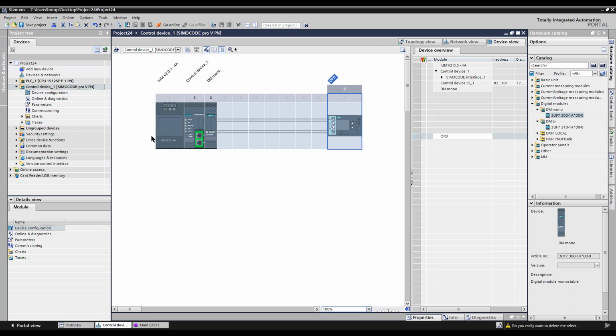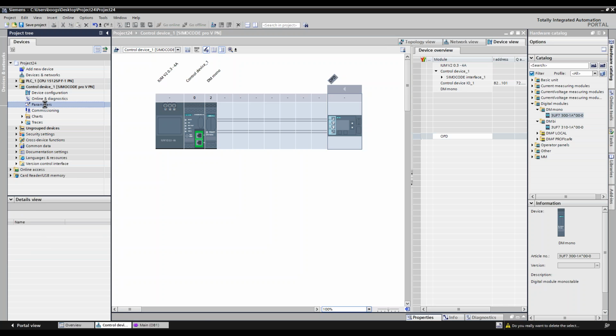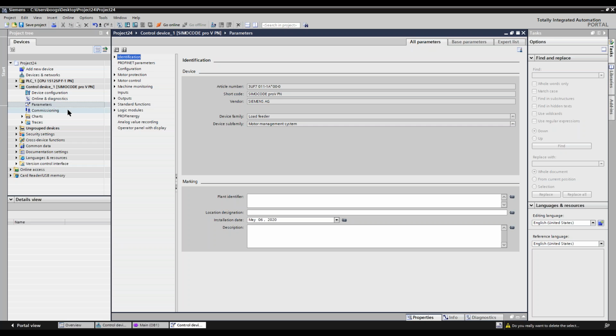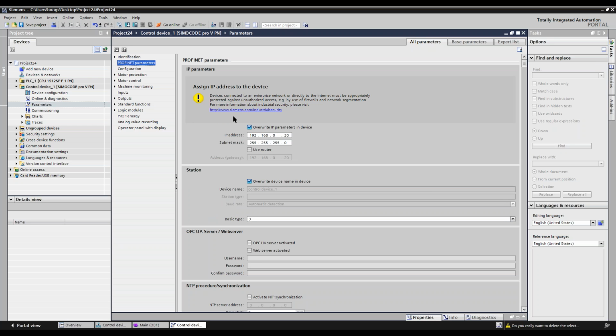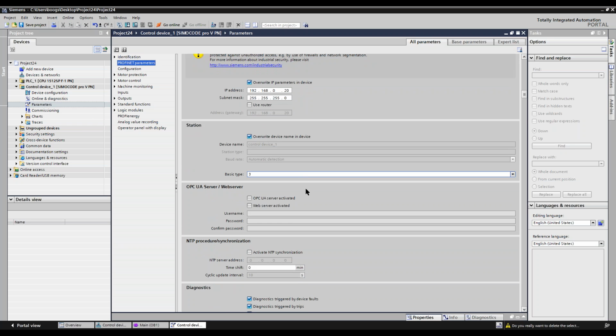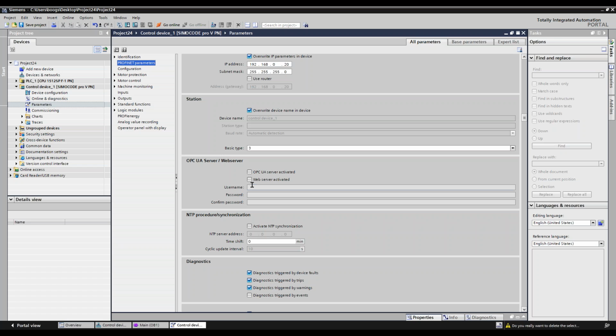But one last thing I want to point out before I do that. I'm going to go over here to parameters. So it kind of acts like a drive. It has parameters and commissioning if you've done a Siemens drive. And then I'm going to go to Profinet parameters. Here's another place to change the IP address. But I'm going to scroll down and let me emphasize this with the Profinet version. Here is the OPC UA and the web server. SIMOCODE pro V Ethernet/IP has a web server. The Profinet has an OPC UA server built in.